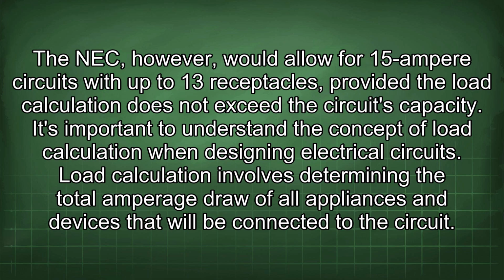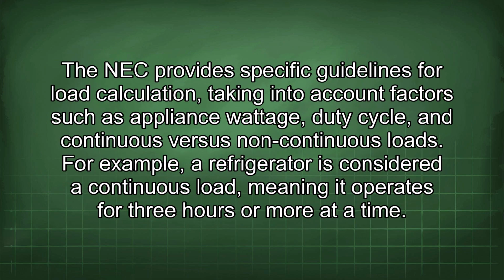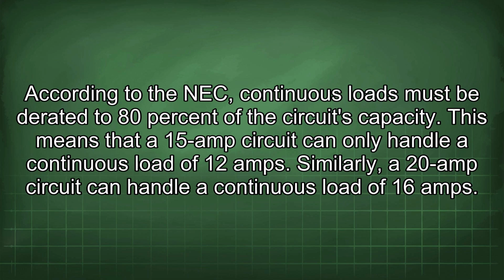Load calculation involves determining the total amperage draw of all appliances and devices that will be connected to the circuit. The NEC provides specific guidelines for load calculation, taking into account factors such as appliance wattage, duty cycle, and continuous versus non-continuous loads. For example, a refrigerator is considered a continuous load, meaning it operates for 3 hours or more at a time. According to the NEC, continuous loads must be derated to 80% of the circuit's capacity. This means that a 15 amp circuit can only handle a continuous load of 12 amps. Similarly, a 20 amp circuit can handle a continuous load of 16 amps.